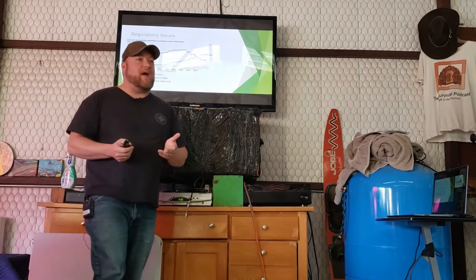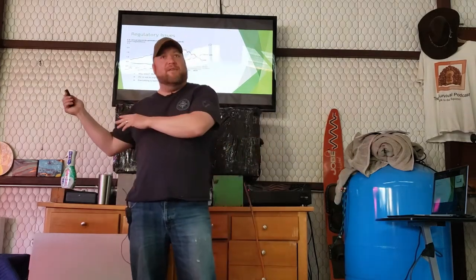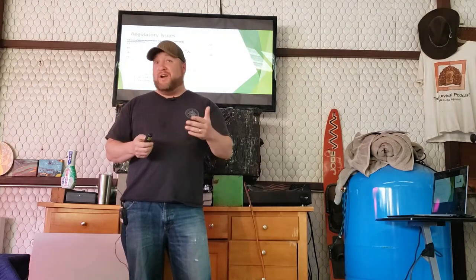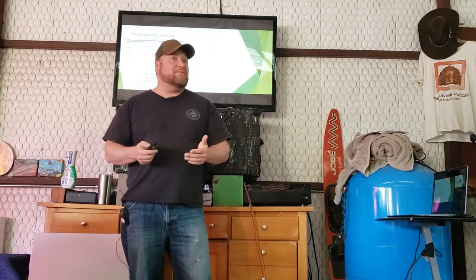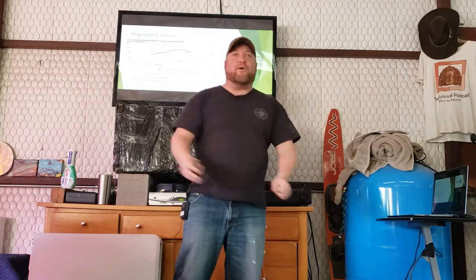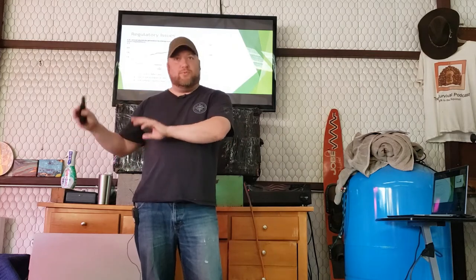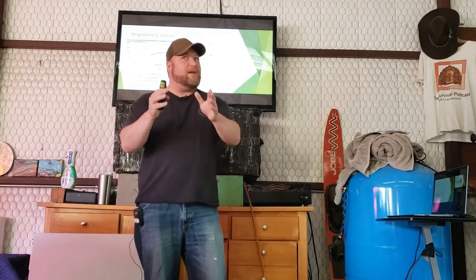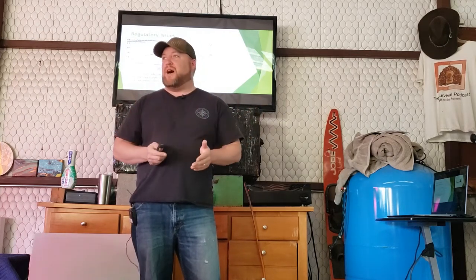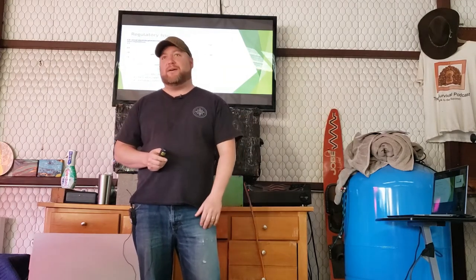You might have a plant that's got four units generating electricity with coal. And in the back, they've got another 16 combustion units that are generating it with natural gas. And so what happens is when one of these units starts getting really bad, they're actively making decisions like, don't fix it, we'll use that one for parts to keep the other three going. And then when the second one goes down, it's don't fix it. Now we've got extra parts to keep the other two. And maybe we can keep these two running, pulling parts off the other two that are down, for a little bit longer than we thought we were going to. But those are the kind of decisions they're making. It's not, well, it's going to cost us $25 million to get this unit back on. They're not doing it.